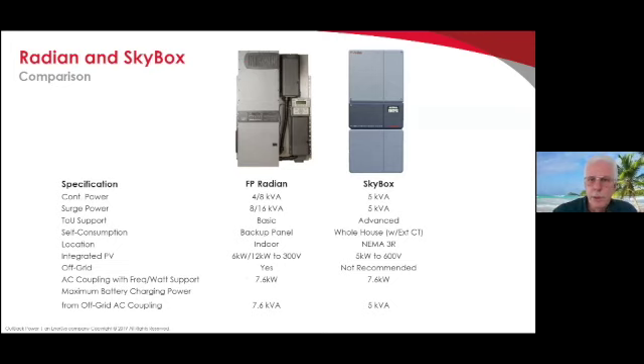So these are the two inverter types that are part of a SystemEdge package. A lot of you are familiar with these products, but just to give you the basic specifications, the Flex Power Radian. So this is a system. It's the inverter, the load center, either 1 or 2 charge controllers, depending on whether you have a 4 kVA or an 8 kVA inverter, and then the Mate3 system controller, okay?